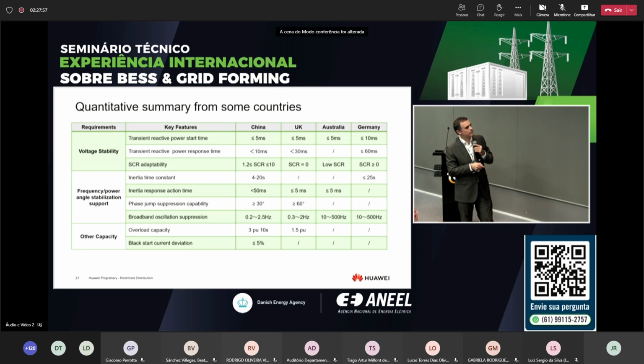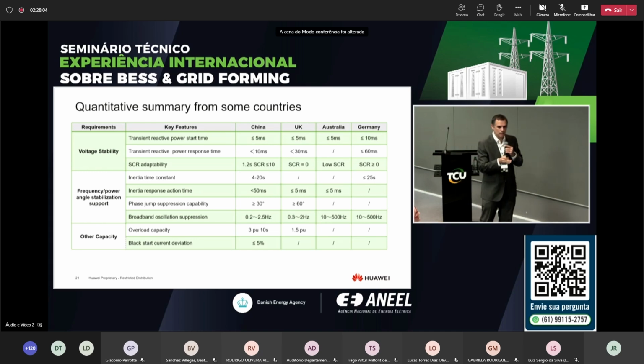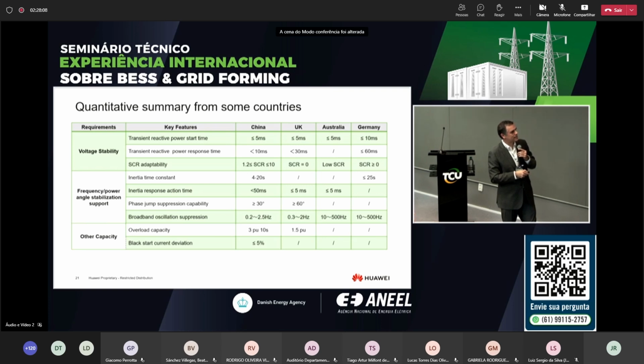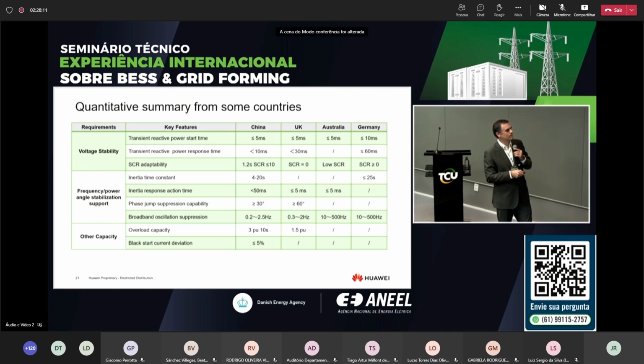The inertia should be in 5 milliseconds as well. If there is a phase jump, you need to still keep working stably. And about overload capacity, in China they are requesting 3 per unit. In the UK, 1.5. In Europe, we are talking about 1.2. The thing is, if there is a fault, we need to inject some extra reactive current to support the grid.